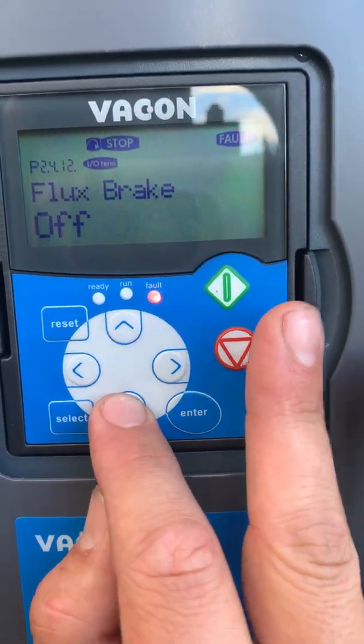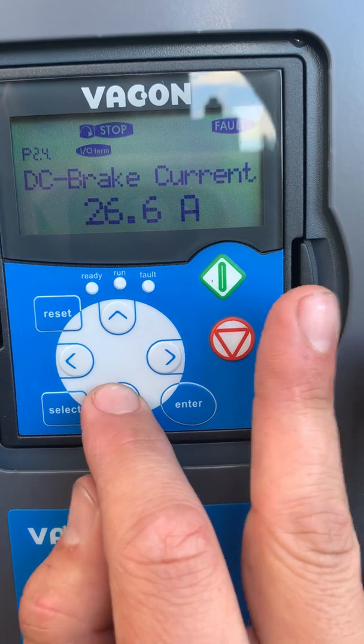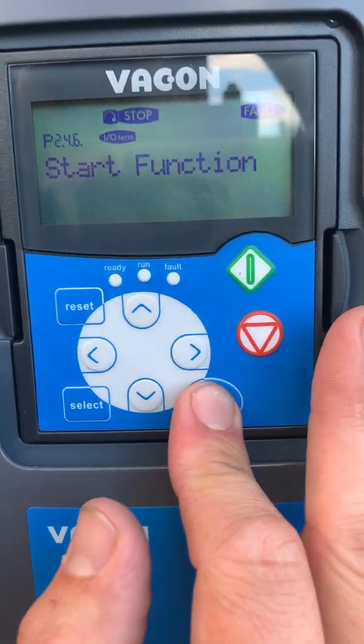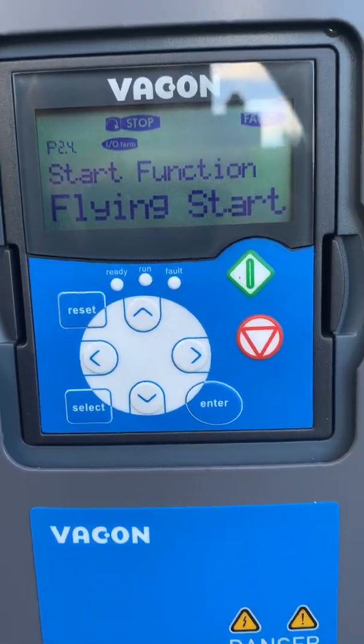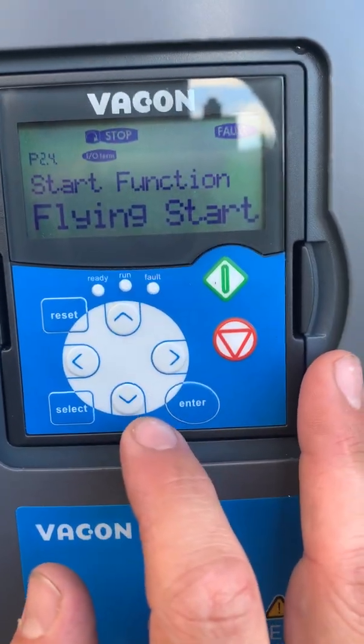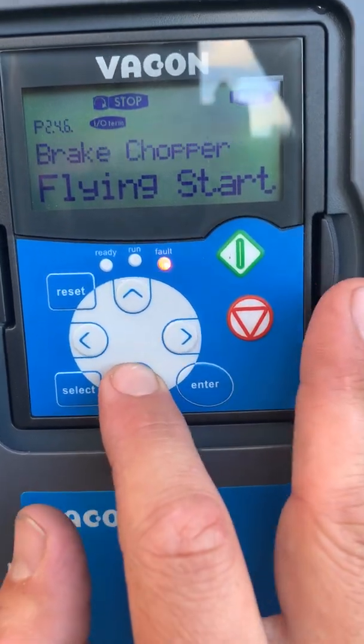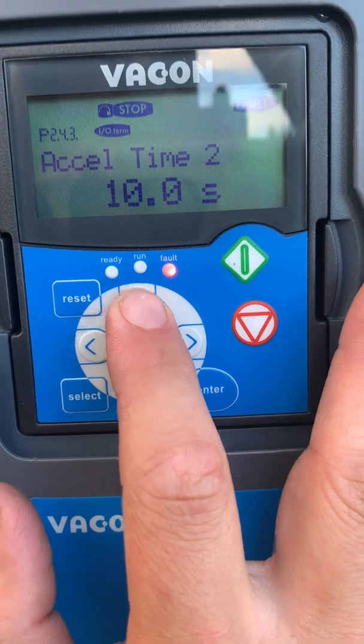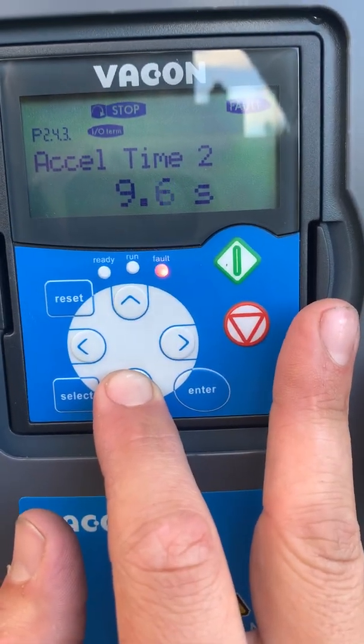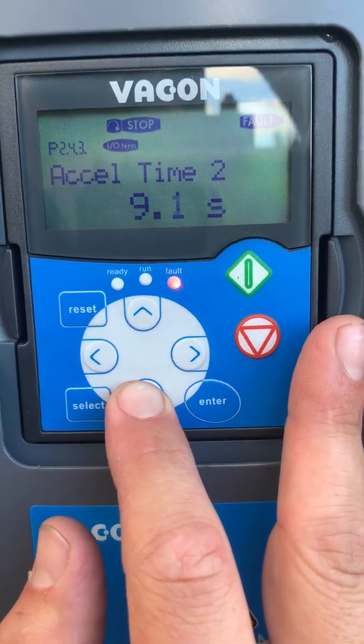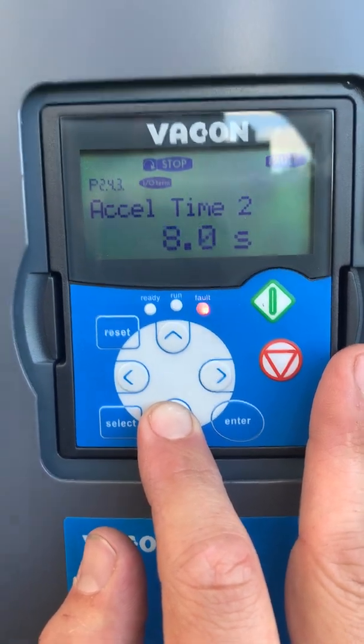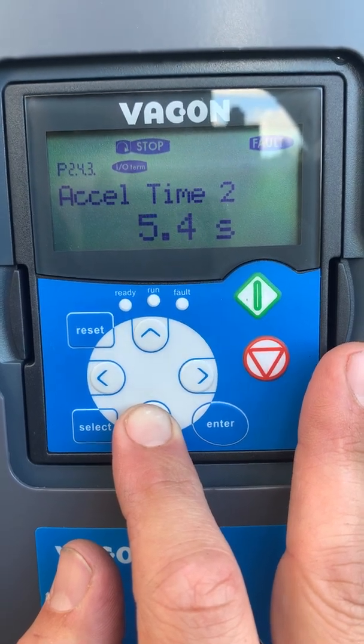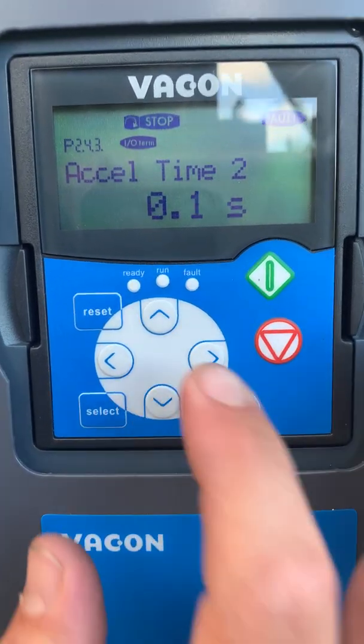We go to drive control and through the ramp shape — we don't change all of these. We do come to the starting function and change it to a flying start. This helps to get the compressor straight up to 30 Hz and not waste time. For acceleration time 2, depending on other speeds, we can lower this secondary acceleration time as well, which will again prevent stall.